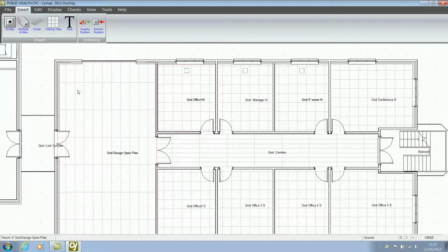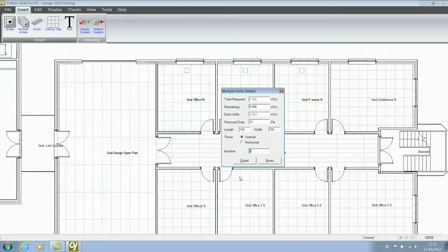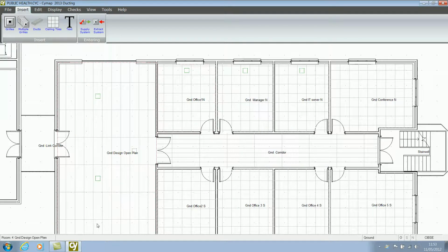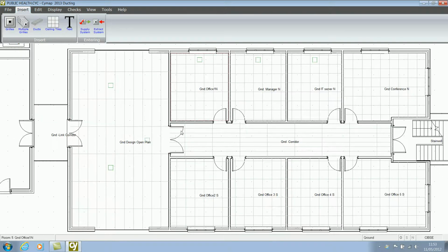if I select the open plan office, I can insert multiple grills using the same principle I did with the extract, and I'm going to put in 3 grills. If I put in a number of grills and select equal, this will then give me the divided flow rate to each grill, and again I can apply the grill size. You can see here the grill is somewhat off the layout, so I can pan across. I can drag and drop the grill to my new location and then edit the grill in the middle.